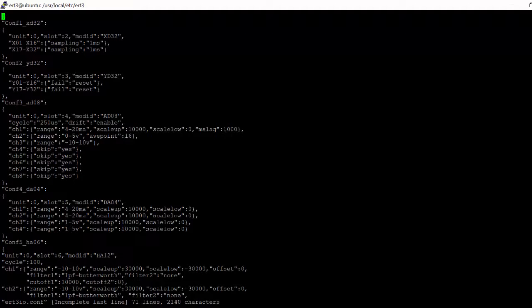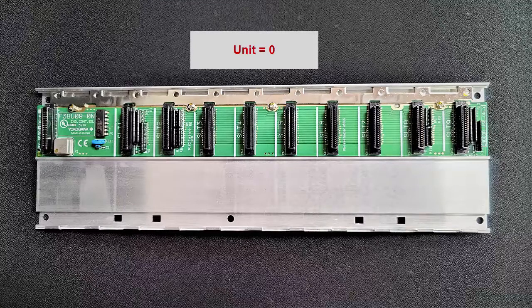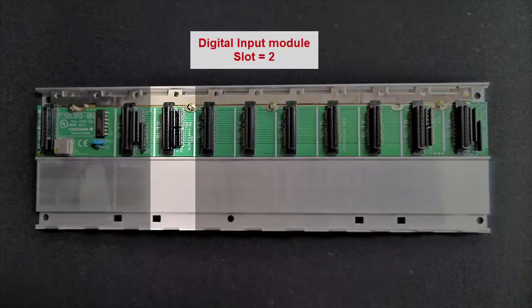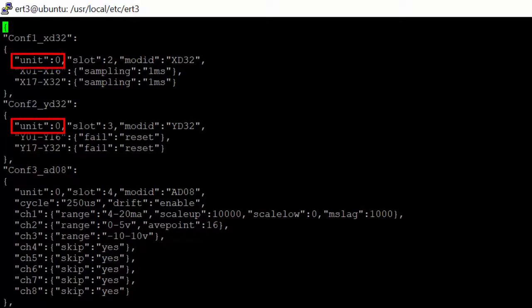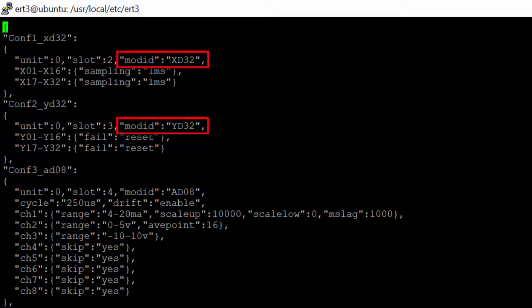In each object we define the details of the module such as the unit, slot number, and mod ID. Unit indicates the unit position — since we have only one unit the value is set to zero. Slot indicates the slot position: the power module is in slot 0, the CPU module in slot 1, the digital input module in slot 2, and the digital output module in slot 3. The slot position for the digital input module is defined as two and for the digital output module as three.